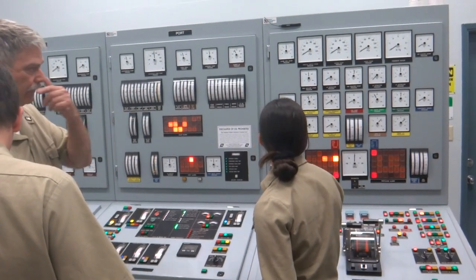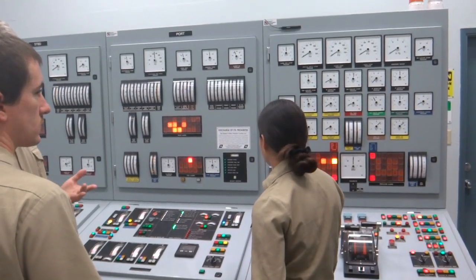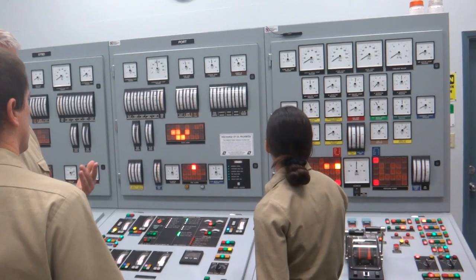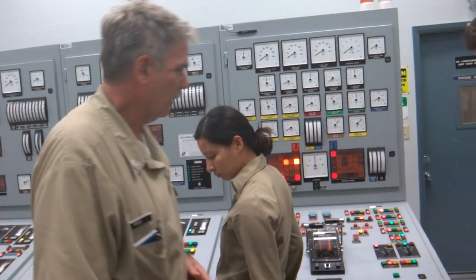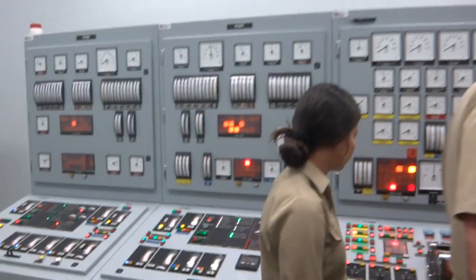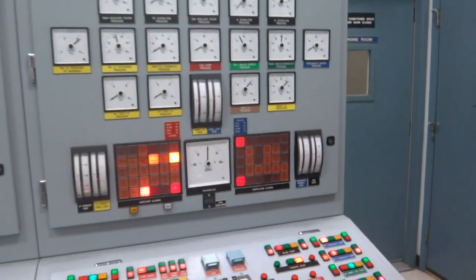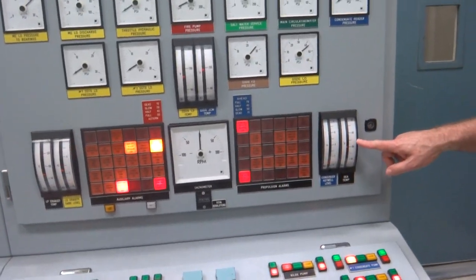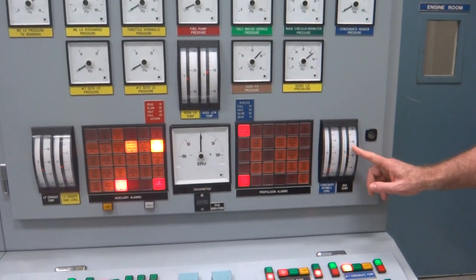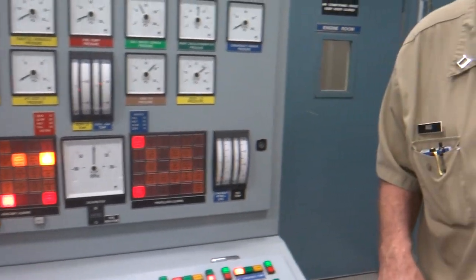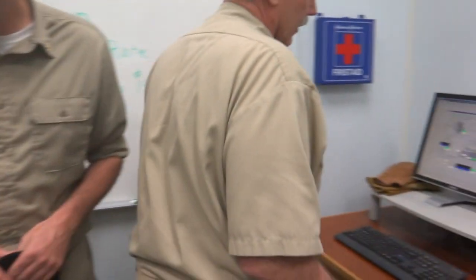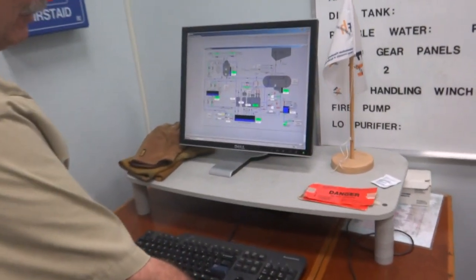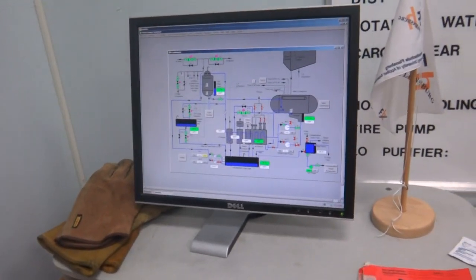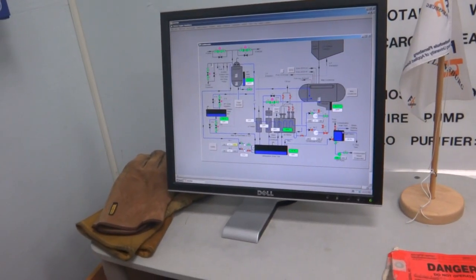We got the 150 on. What else can we do? We got lube oil. We can check our hot well level. Here's your hot well level right here. Hot well level and C-temp. So at this point, do we have enough in a hot well to do anything with? It says we got 0.5 inches. It'd be nice to have more, but we can live with it.